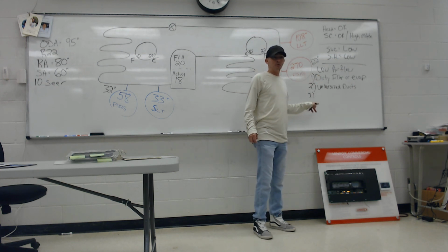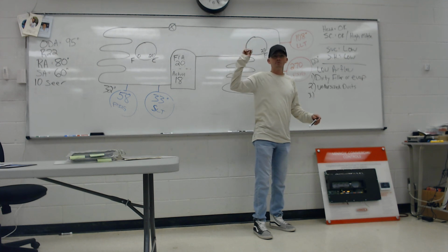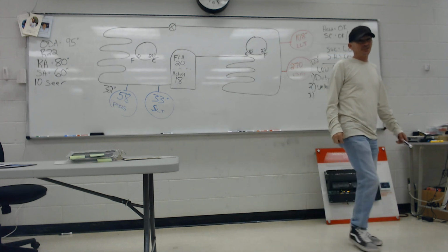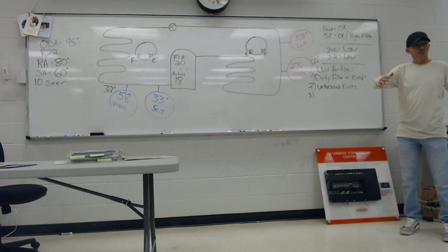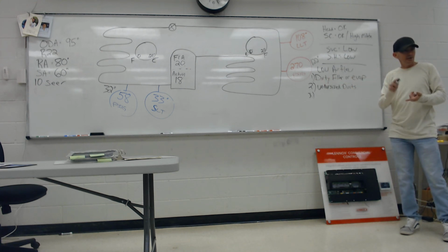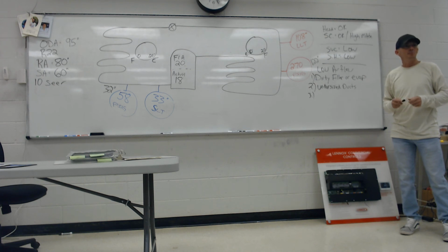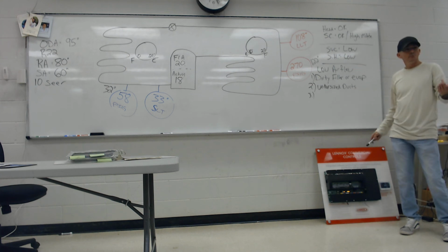What else will be an airflow issue? Let's think commercial rooftop equipment. Leaving a panel off the unit. Yeah, that'll definitely do it. Strip out screws, panels laying off, the blower just sucking in a bunch of air instead of actually pulling it through the evaporator. Every package unit that I know of, just about, the evaporator's in the return. Which also means you need a P-trap on your drain on every single package unit. Panels off, what else?